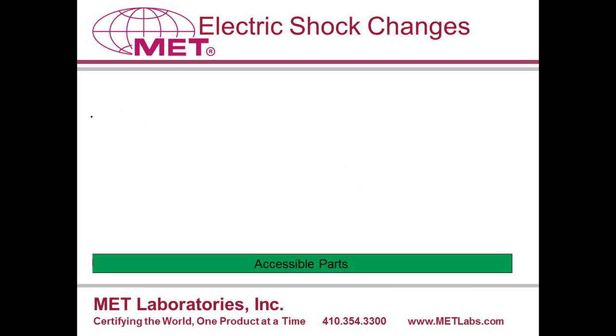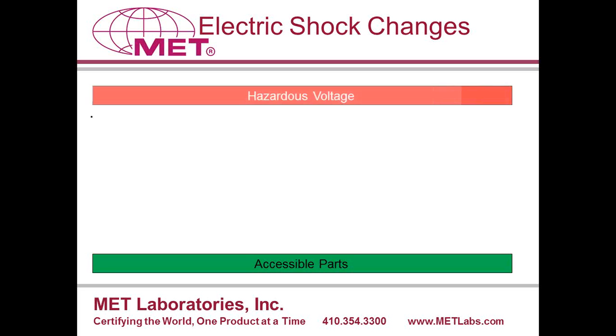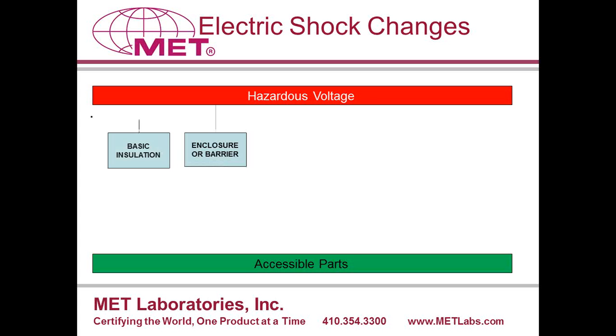I want to review means of protection. All accessible parts must have two means of protection against electric shock hazards, so that even though a hazardous voltage, say 120 to 240 volts, is coming into the product, a low voltage, such as 30 VRMS or 60 VDC, is all that you can touch, even if there's a fault in the equipment. The most obvious primary form of protection is the enclosure. The most common primary protection is basic insulation, such as what you have between a transformer or optocoupler, or even space. You can also use protective impedance or series resistance.